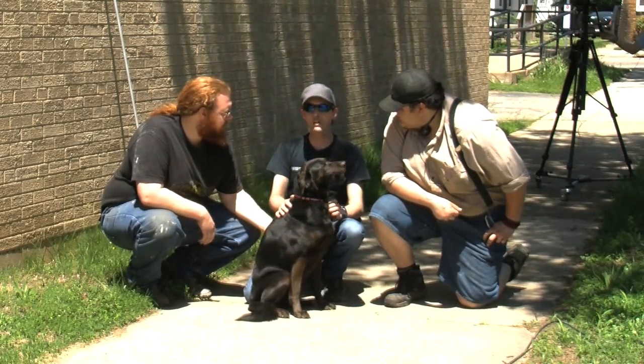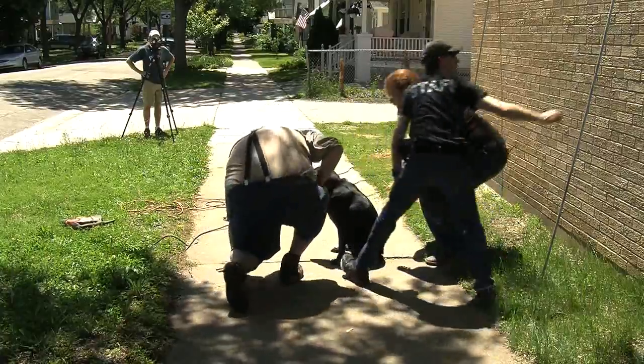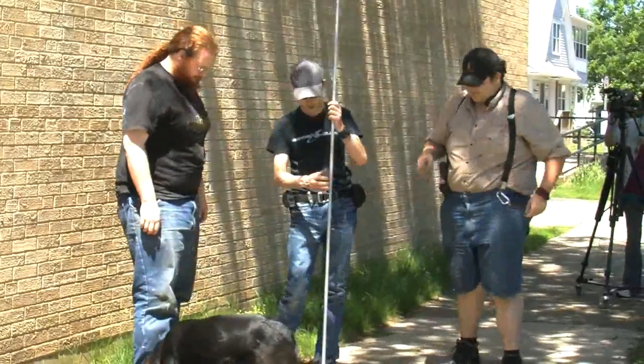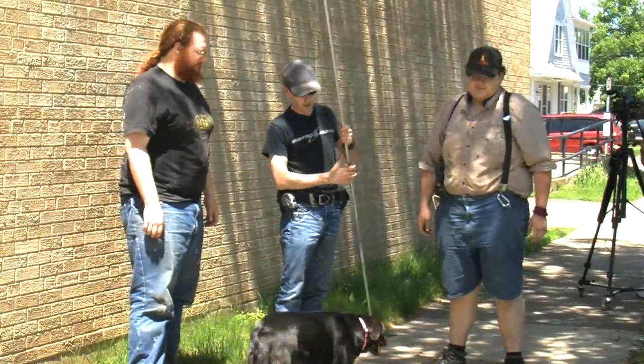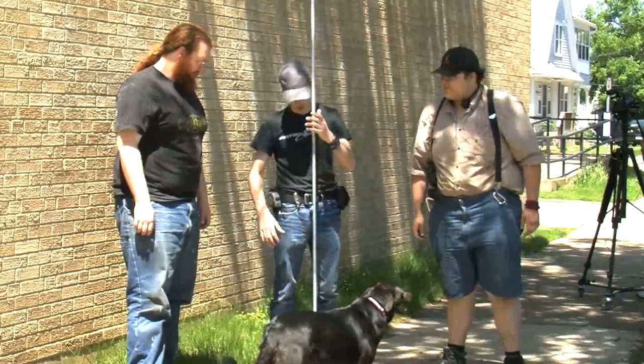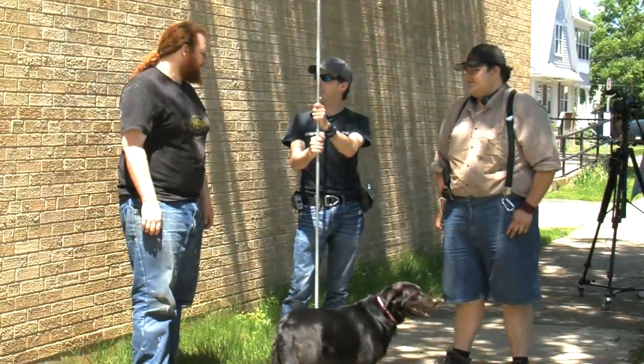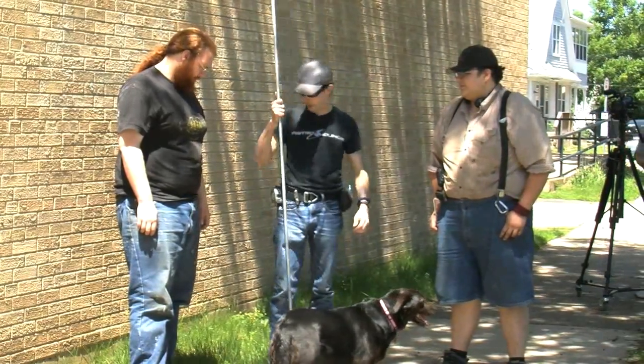So we're going to start by driving ground rods — this is the beginning of it all. We've got these, which we got at our local electrical supply place. It's a standard 5/8 inch ground rod. It's got a pointy end, it's got a round end, and they come in two flavors — copper and galvanized. All they had was galvanized. I wanted copper really bad, but this is what I'm stuck with, so we're going to use these.